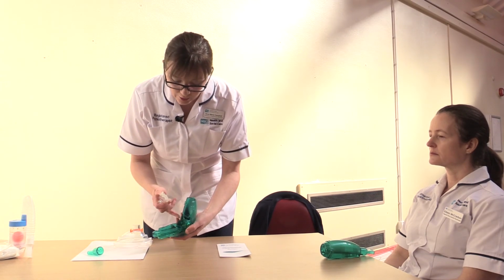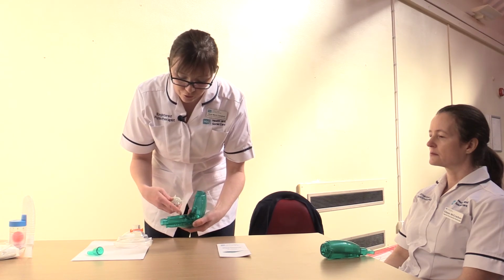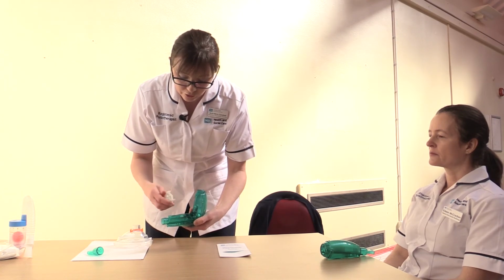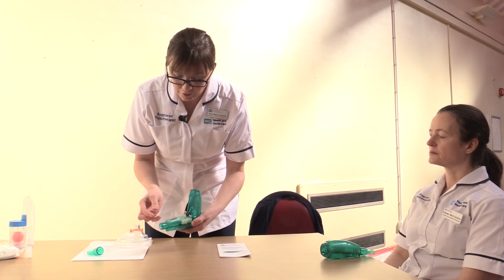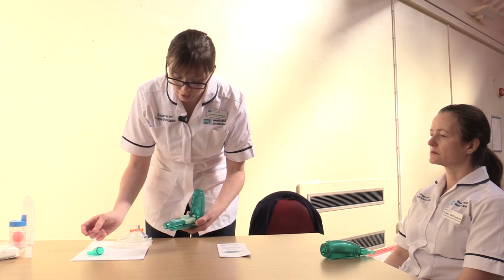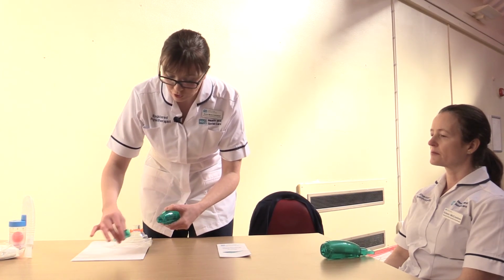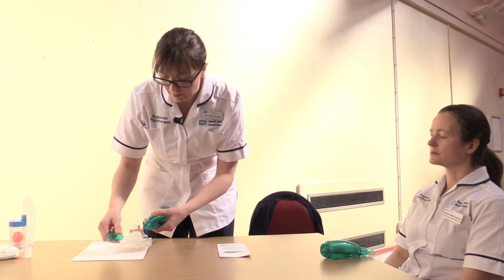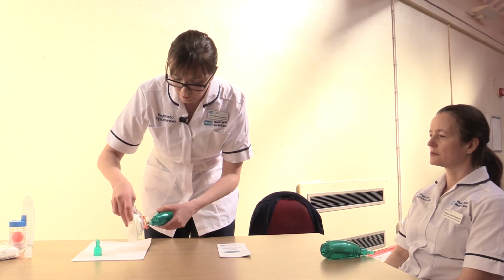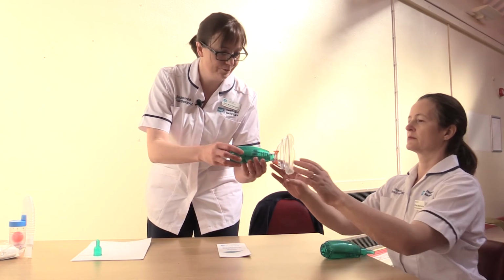they've been cleaned. Got a little magnet here and a bit of metal here. It's really important that they're dried thoroughly so they don't rust, otherwise that will affect the mechanism. So when putting it together, it can only go one way, the rocking device. You pinch that down, a little bit of pressure here, and then put the mouthpiece on over that lip. Okay. Similarly, this is how the face mask is put on. Thank you.